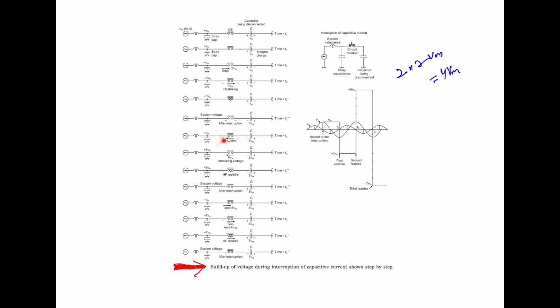The gap is stressed to the voltage of 4 Vm applied across the contact gap, and the peak value of the transient restriking voltage is 2 times that, that is 8 Vm. So the restriking voltage is 8 Vm in this case. However, since the RHS of the contact gap is constrained to minus 3 Vm, a restriking voltage of 8 Vm is achieved by the LHS at 5 Vm, assuming a high frequency discharge takes place just after this instant t3. After the instant t3, the RHS end of the contact attains a voltage of plus 5 Vm as shown here.